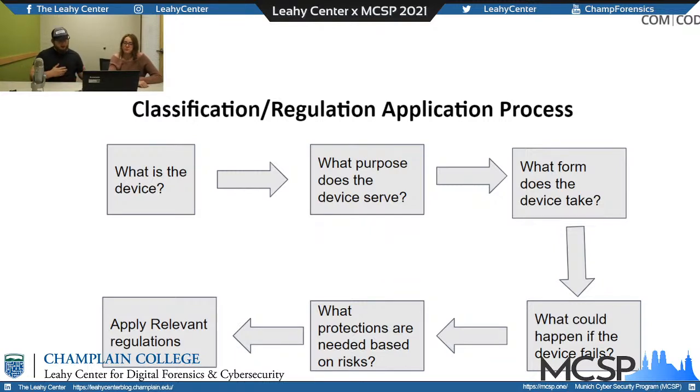So you need to figure out where all the risks are, through either pen testing or analysis or some method that you have to have documented. And you need to have controls to protect from that. So, signed updates. Only receiving messages that are authorized by a certain user. Username and password. Encryption. Backup. Fail-safes, so that if one part of the pacemaker doesn't work, the whole thing's not going to collapse immediately. There'll be some time to get it worked out and fixed.